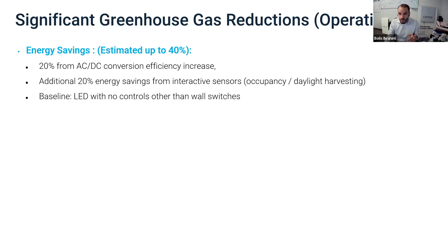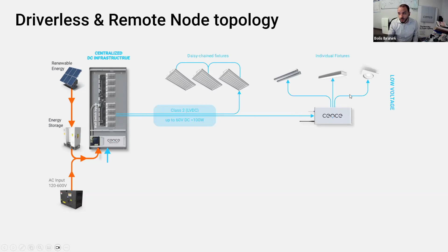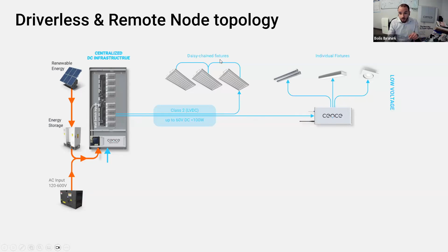There are two topologies for direct current power distribution for any type of device, whether lighting or not. One is a driverless bus topology, the other is point-to-point with an external DC to DC driver - many people make these. For example, we just did a big project with Acuity Lighting. Acuity has a fantastic DC-DC driver that goes onto luminaires, delivering 57 volts, and you put these on a bus. This lets you individually address devices, or if devices have different voltages or current ratings, handle that too. If devices share the same voltage and current, you can put them on a bus together.